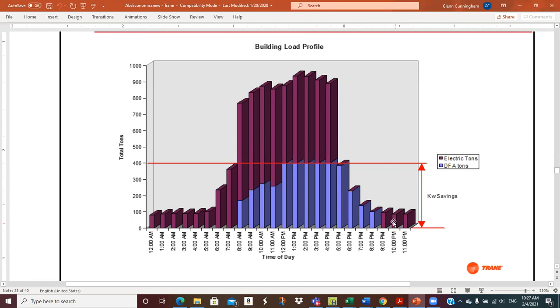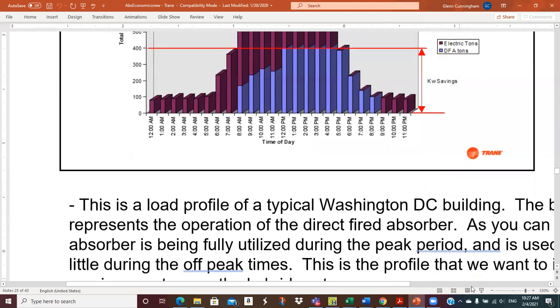And, you know, if you had this operating, you probably would want it to happen automatically, where you had automatic controls that were programmed, based on time of day. The system knew, okay, we want to max out the centrifugal over here. And then all of a sudden, right here, now we want to max out the absorber and trim, and all that sort of thing happens automatically. So that's pretty cool.